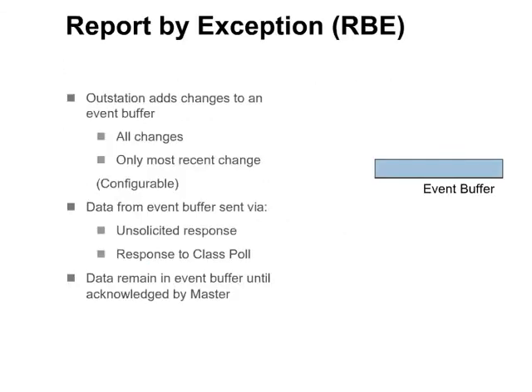DNP-3 supports report by exception, or RBE. With RBE, the outstation only reports data changes. RBE can be used with polling or with unsolicited responses. With RBE, the outstation adds changes to an event buffer. It may add all changes or only the most recent change, and which type is added can be configured per data type. Data from the event buffer can be sent via unsolicited responses or in response to a class poll. The data remain in the event buffer until acknowledged by the master.